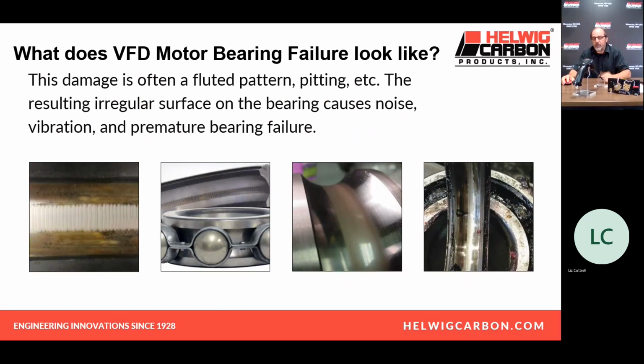What does VFD motor bearing failure look like? Typically, you're going to see a fluted pattern like you're seeing on the left. That fluted pattern will be on the inside and outside of the raceway. The ball bearings themselves will become frosted. If you look at these elements very, very closely, you'll see that frosting and even the pitting on the ball bearings and the washboard that you see on the raceway. If you look at them very, very carefully, they are actually microscopic pits in the bearing and roller elements, and that's where the noise and all the other bad things come from. The other thing we're going to look for right away is burnt grease.